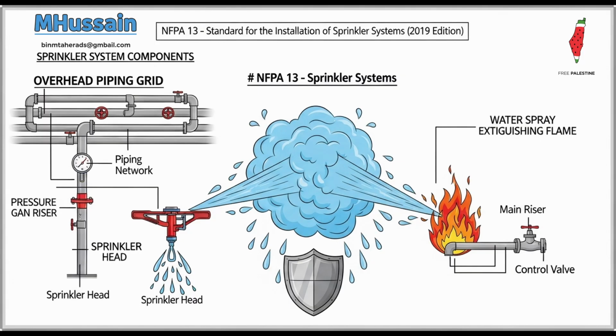Let's briefly touch on piping installed above ground now, particularly systems that might use antifreeze. Sure. Where temperatures cannot be reliably maintained at or above 40 degrees F, that's 4 degrees C, the system must be protected. Usually this means using a dry pipe or pre-action system, basically. No water sits in the pipe until the system actually activates. Antifreeze is permitted in unheated areas, but it has to be properly mixed and certified. And there was a critical update regarding testing in a specific type of sprinkler head there, wasn't there? Yes, very important. If the system is hydrostatically tested with plain water, that water must be completely drained from the entire system afterward, especially if you have pendant sprinklers, to prevent dilution of the antifreeze solution later.